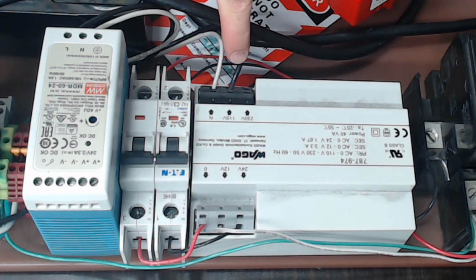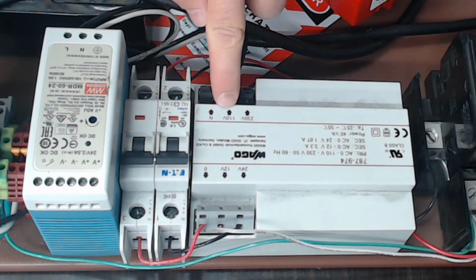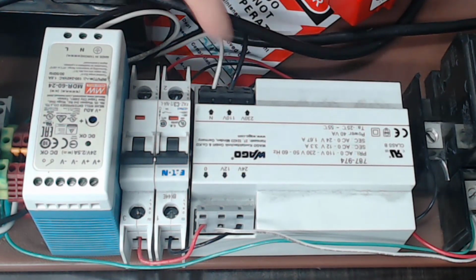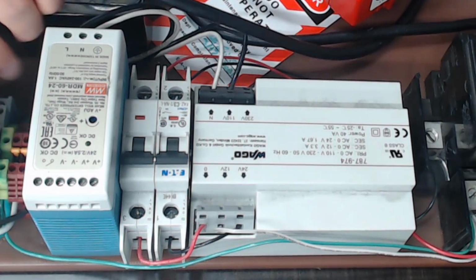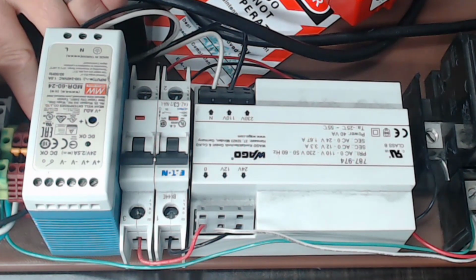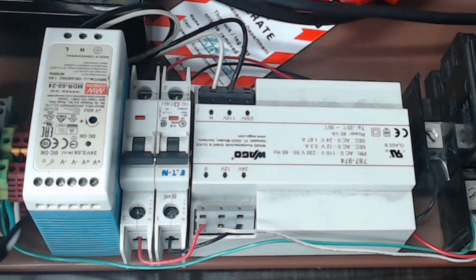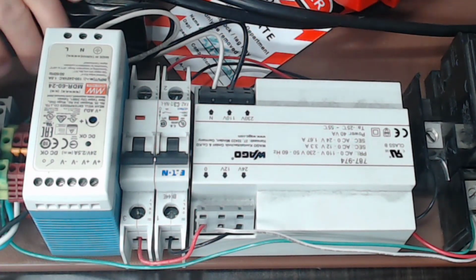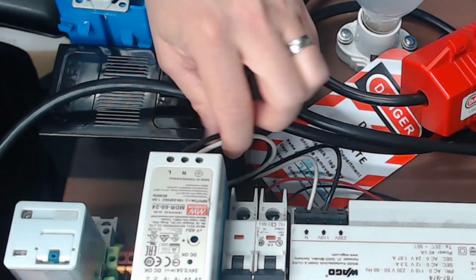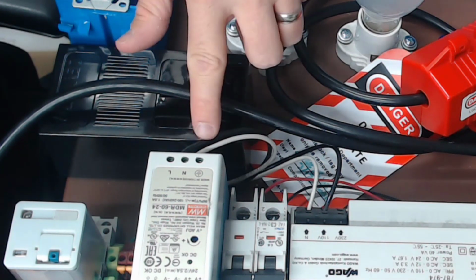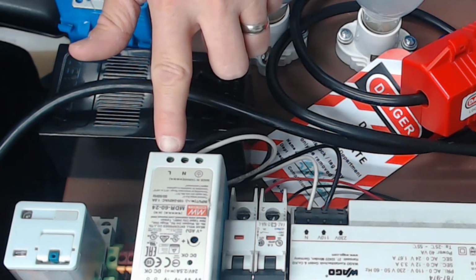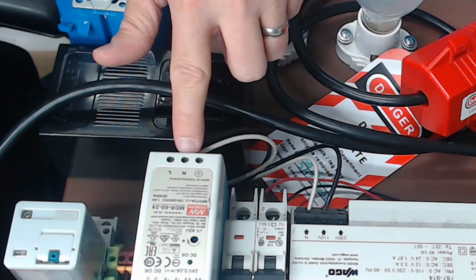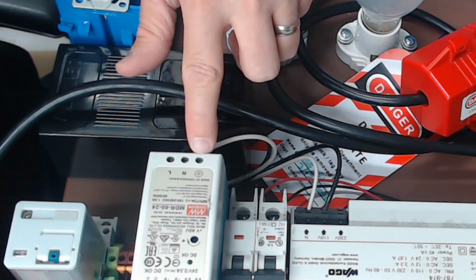On this side we have our 120 volt coming into our 24 volt transformer. We have the black here on the 110 and the white on the neutral. That comes into our terminal blocks here. The black is for the hot and the red is for the neutral, which feeds into our plug. The green is for ground. We also have some black and white and a green coming into our 24 volt power supply. The black comes into L for line, the white comes into N for neutral, and the green comes into ground.